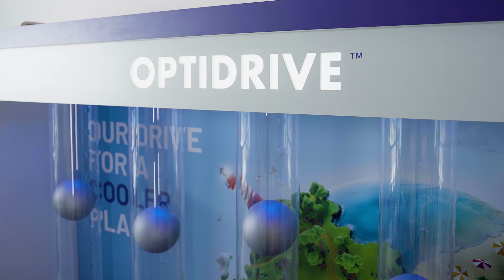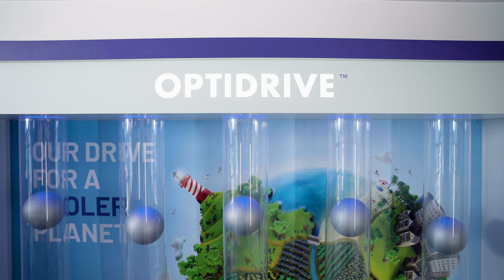We control all of those drives in variable speed using the height sensors for the balls at the top. So the direct online is used as the reference to give us a starting position, and then each of the drives operates automatically using a PID loop to maintain the height of the ball at the same position in the tube.